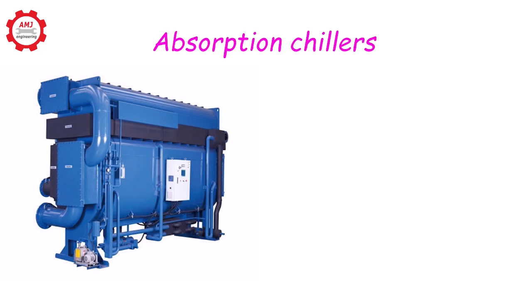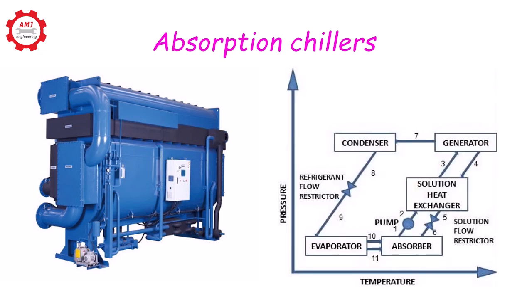Absorption chillers: The absorption cycle uses heat to generate cooling using two media - a refrigerant and an absorbent. Water-lithium bromide is the most common refrigerant-absorbent media pair, but other pairs can be used.